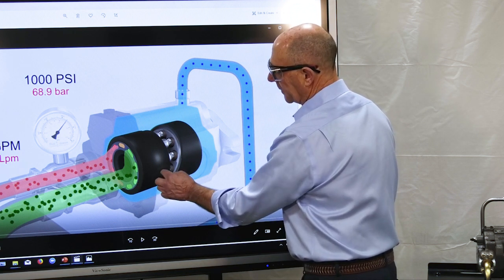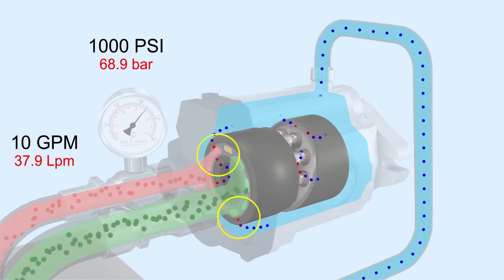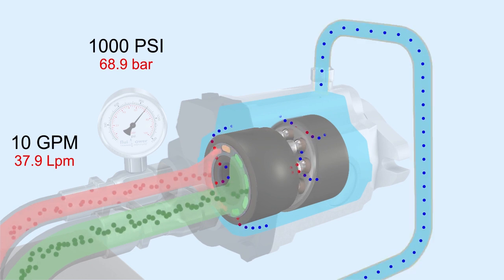The green is the intake, the red is the discharge. As the barrel is rotating, you will see in real time where this pump is leaking internally — between the barrel and the wear plate, between the piston and the bore, and through the center of the piston between the piston slipper and its wear plate. Leakage between the piston and its bore goes into the case and finds its way back to the hydraulic reservoir through the case drain line — and this is typically where the industry encourages us to do the volumetric efficiency test on this type of pump.